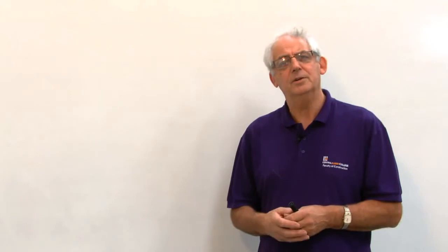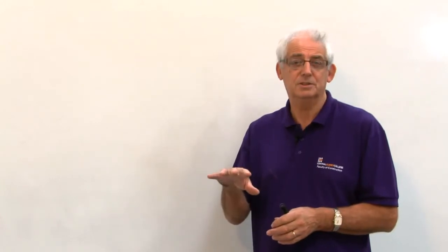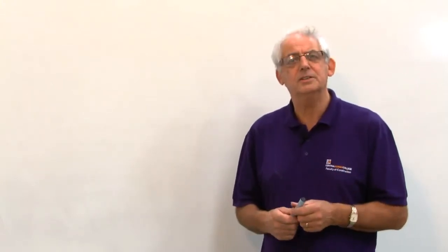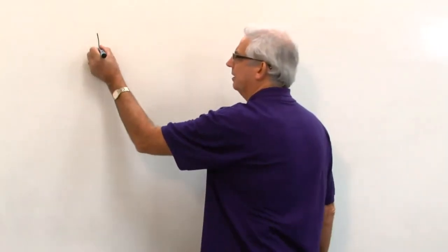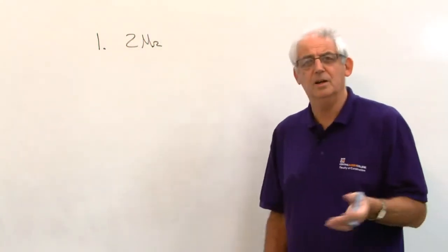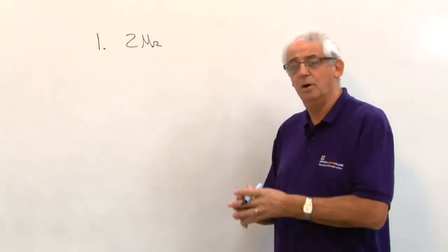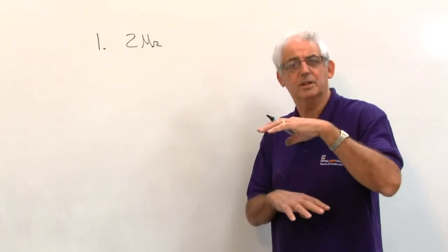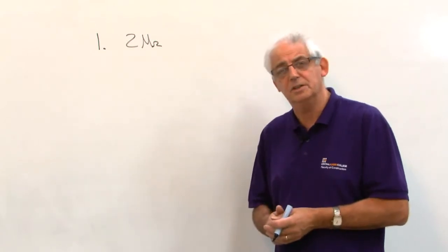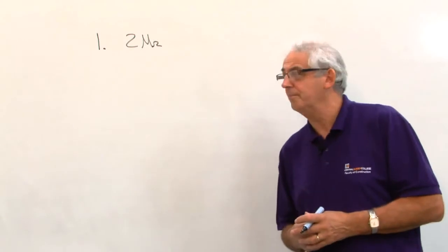Now, of course, if we're measuring separate circuits, we need to carry out a calculation when we finish to make sure that the overall insulation resistance for that system isn't below 1 megohm. Let's just assume, as an example, we've got a situation where we've got 4 circuits. If the first circuit is 2 megohms, we know it's very low, but this is purely a calculation to show you why we need to do a calculation of the whole of the installation when we've finished. Because some installations could have 10, 15, 20 circuits, which of course will reduce the resistance a lot.